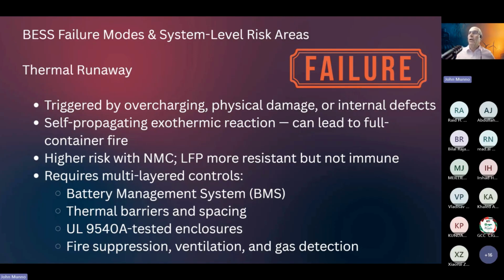Some other things that we're seeing now, and I'll mention this since I said earlier that I've been interviewing entrepreneurs and developers of new techniques and new equipment. A few companies that do battery monitoring have reached out to me. So I see that one company, Validica, will take just your raw SCADA data, nothing new needs to be installed at your facility, and they will analyze it on their end, as opposed to these systems that depend on gas detection, that's telling you that a problem has already occurred, that there's already an active thermal runaway by the time you're detecting gas. And the manufacturers of the gas detection systems talk in minutes, how many minutes after the thermal runaway starts that we can detect the gas.